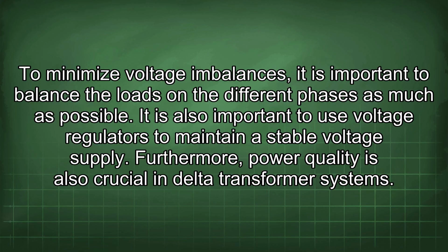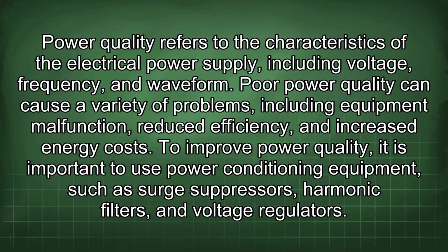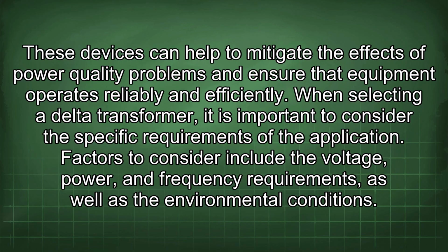Furthermore, power quality is also crucial in delta transformer systems. Power quality refers to the characteristics of the electrical power supply, including voltage, frequency, and waveform. Poor power quality can cause a variety of problems, including equipment malfunction, reduced efficiency, and increased energy costs. To improve power quality, it is important to use power conditioning equipment such as surge suppressors, harmonic filters, and voltage regulators.